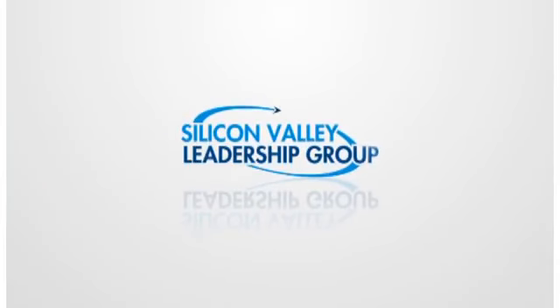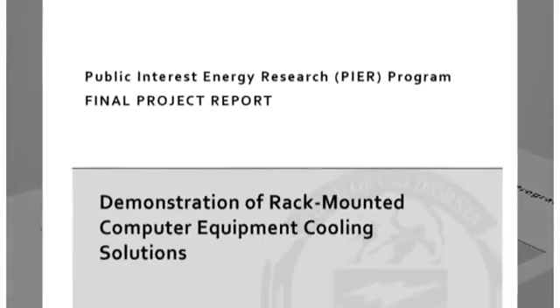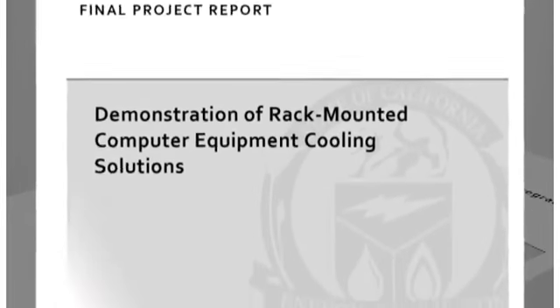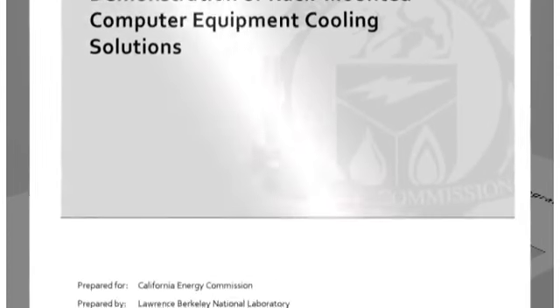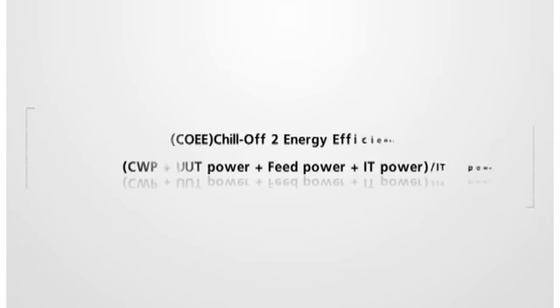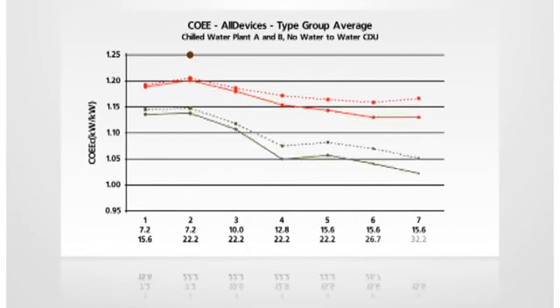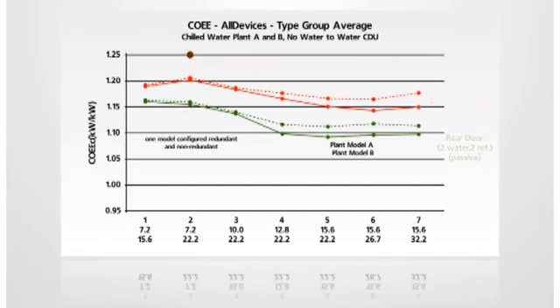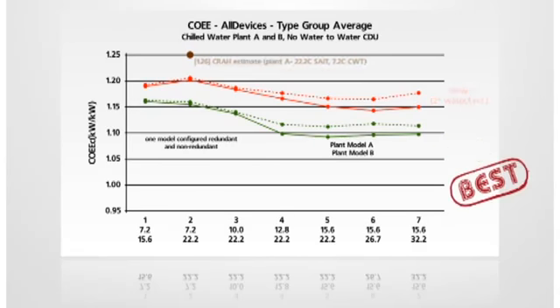Results of the SV-LG Chill-Off report indicated significant performance variations among CRAH in-row and RDHX in-rack cooling methods. According to the SV-LG Chill-Off 2 demonstration project, it was discovered that the COEE performance of the RDHX with cooling at rack level was outstanding when compared to the other cooling methods, which use air to transfer the heat generated by servers.